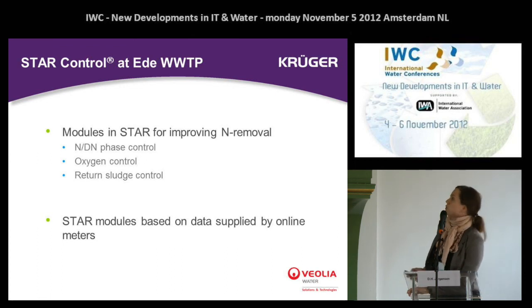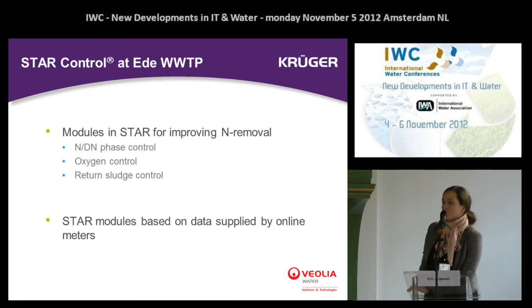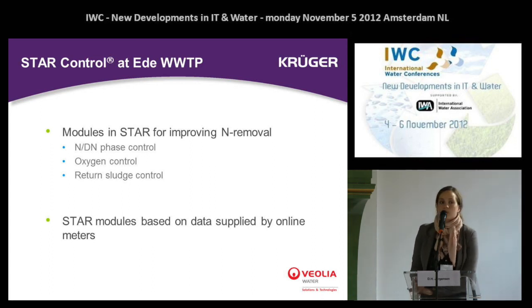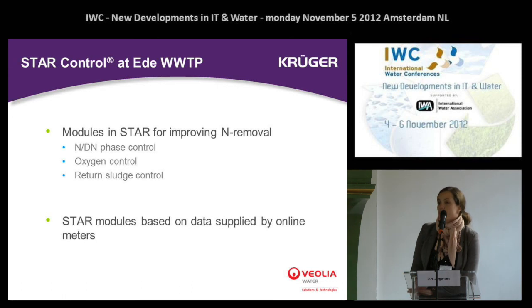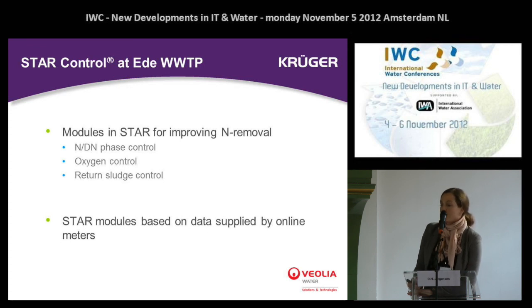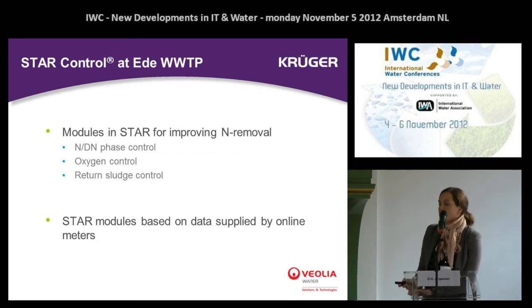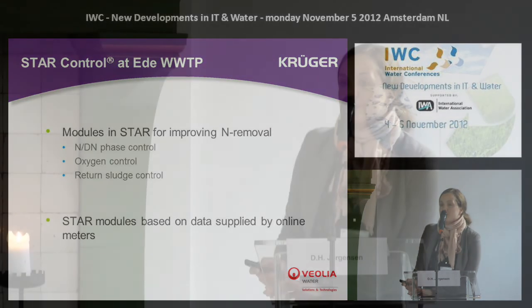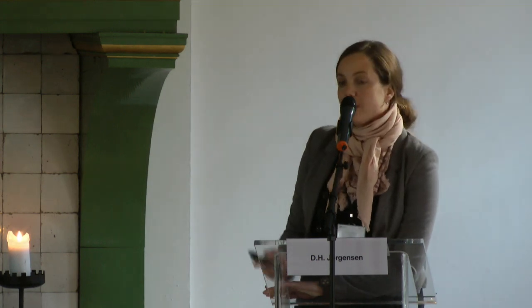The STAR control at Ede hosts the following modules: N/DN phase control, oxygen control, and return sludge control. The phase control manages the length of phases and whether operation should be in nitrification or denitrification. The oxygen control manages the dissolved oxygen set point delivered to the process tanks — in this case with many individual set points per tank. The return sludge control is based on suspended solids in the return sludge flow and sludge blanket meters at the final settling tanks. It is important to note that STAR control is based on data supplied by online meters.